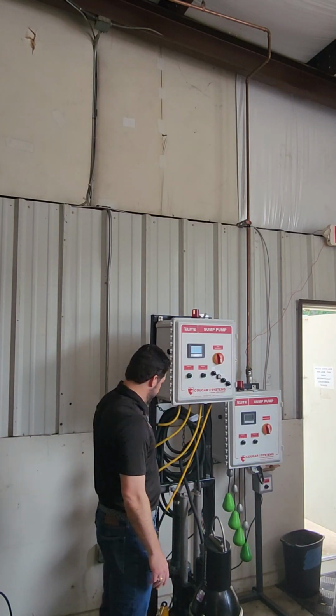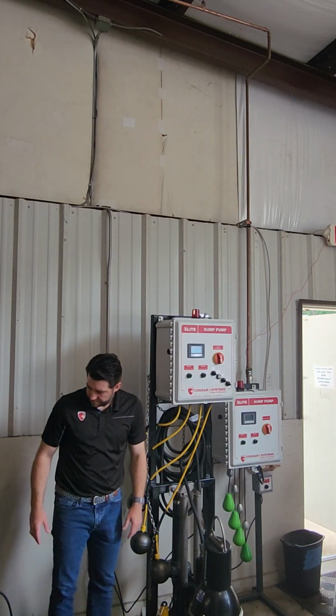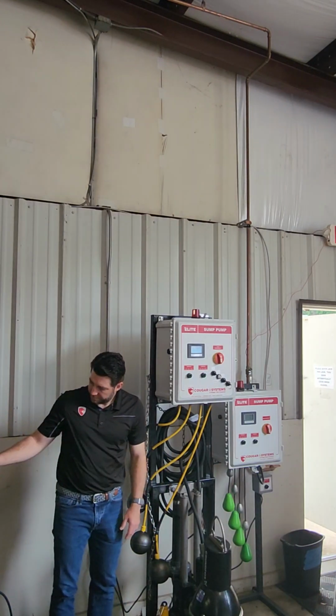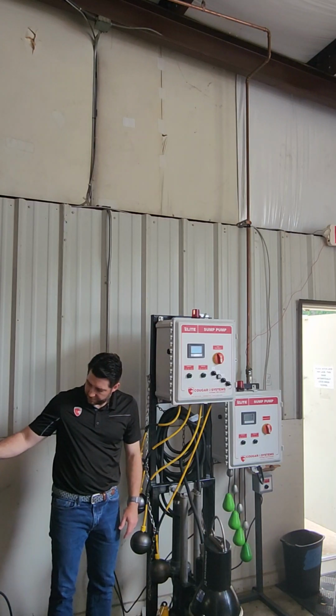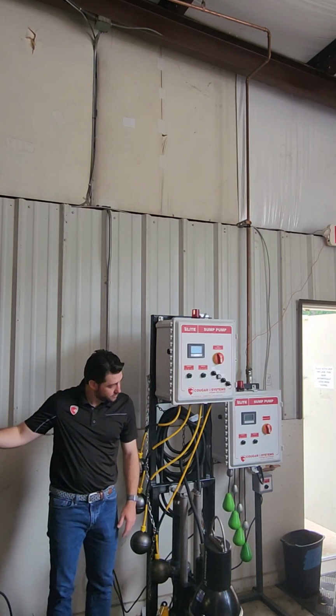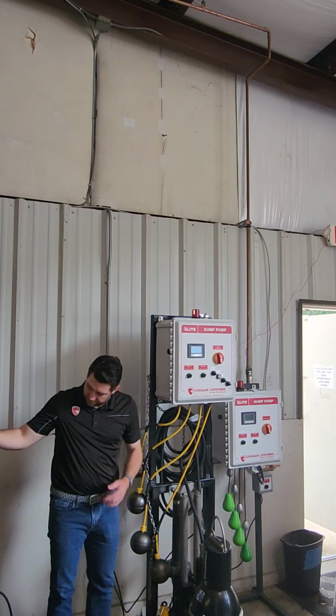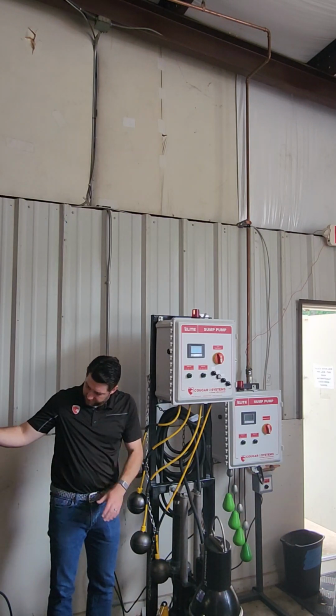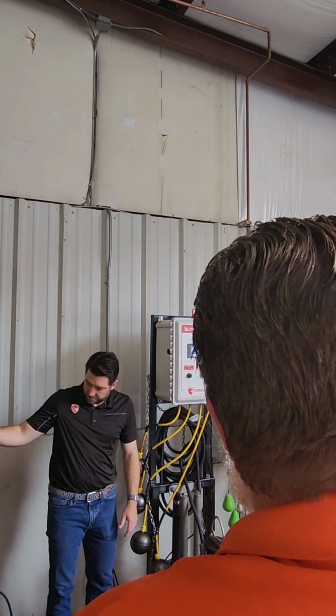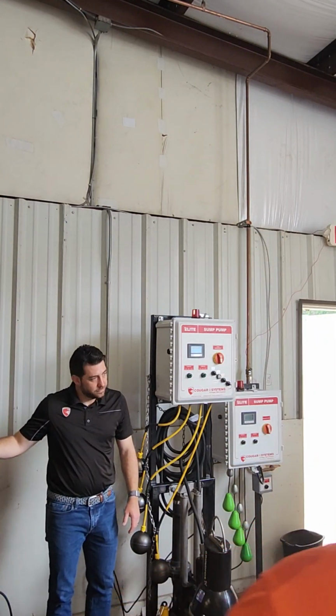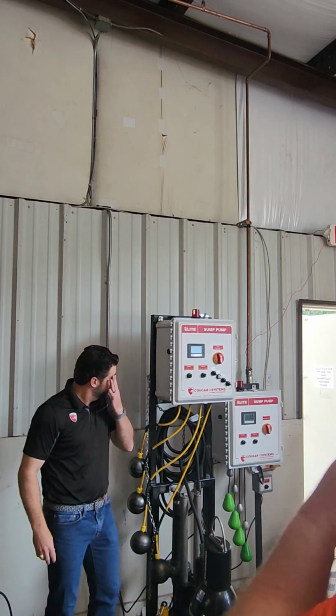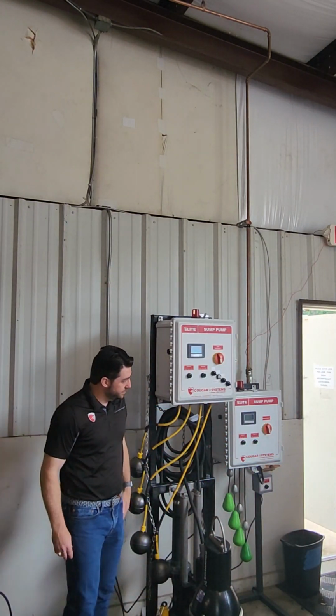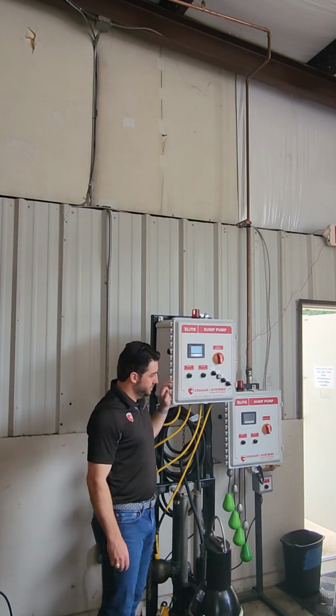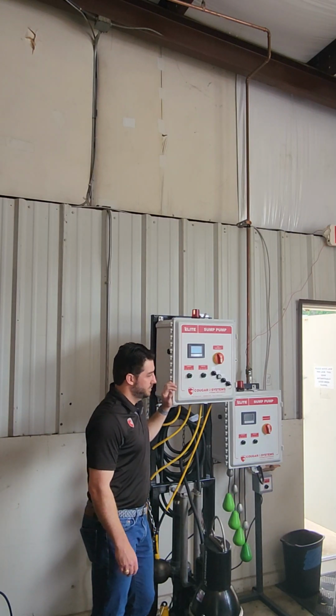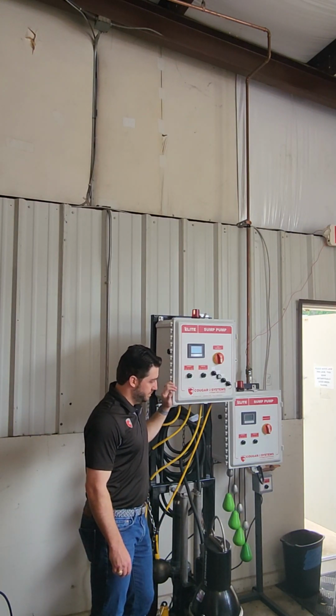I always do it like the weighted ones, just one on top of each other. Where the weight selects the other one, then raise the second one up above the weight. So that's a good distance right there. Gotcha. So just do one at a 45-degree angle for it to activate. Yeah. And then the other one, so that gives you a good pump down. And then again, like you said, it depends on the space of the pit. The height doesn't matter, it's just the diameter, the width. Because you never want it to rest on top of the pump and lock it. If you set the offload above it and it's always submerged, it's okay.